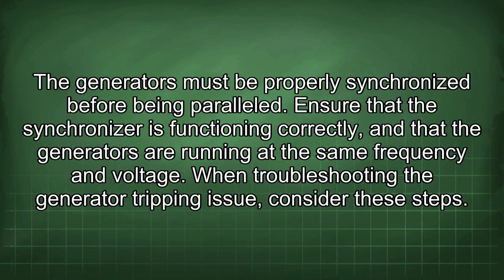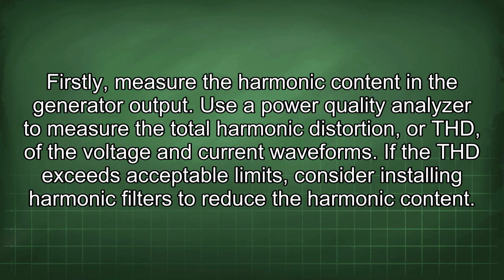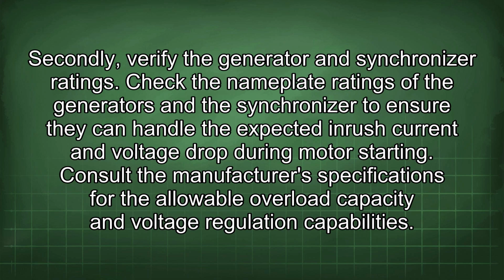When troubleshooting the generator tripping issue, consider these steps. Firstly, measure the harmonic content in the generator output. Use a power quality analyzer to measure the total harmonic distortion, or THD, of the voltage and current waveforms. If the THD exceeds acceptable limits, consider installing harmonic filters to reduce the harmonic content. Secondly, verify the generator and synchronizer ratings. Check the nameplate ratings of the generators and the synchronizer to ensure they can handle the expected inrush current and voltage drop during motor starting. Consult the manufacturer's specifications for the allowable overload capacity and voltage regulation capabilities.